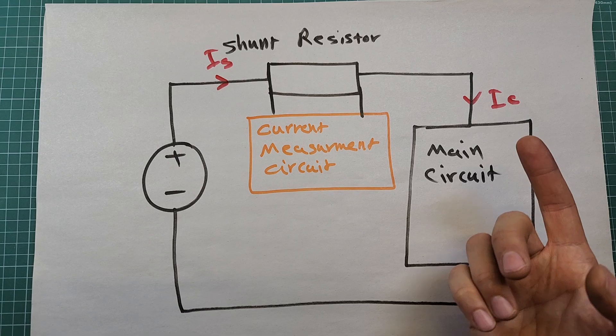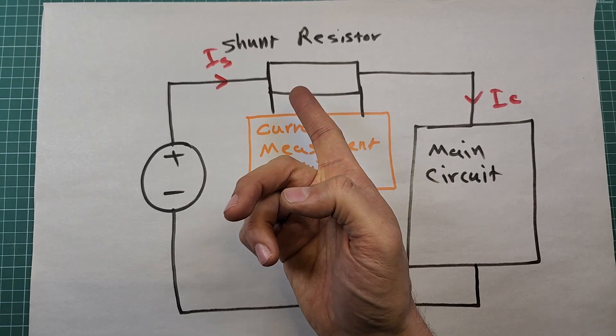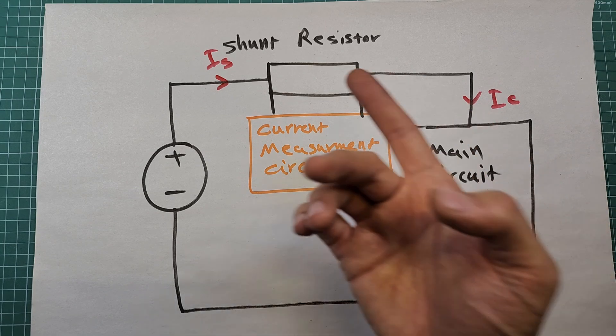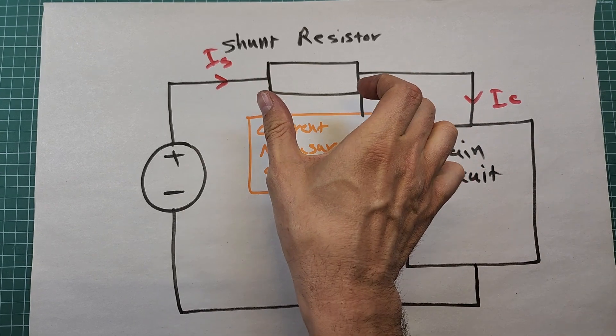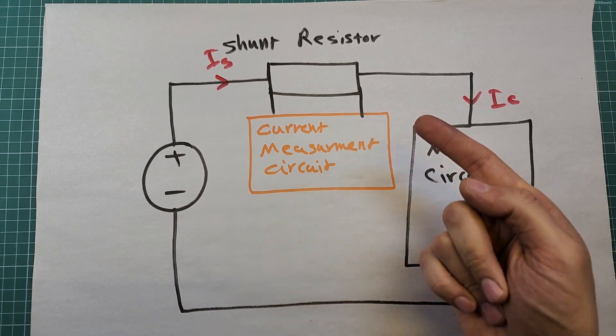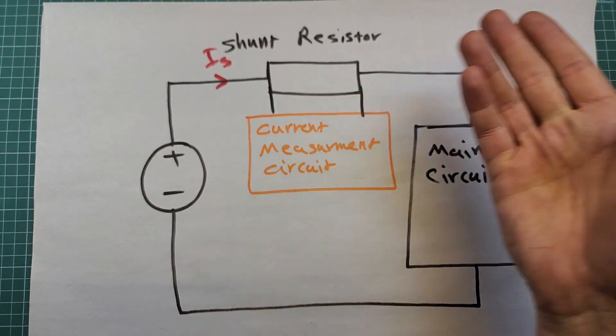In many cases using a shunt resistor is the best method, but it also has disadvantages that make us not want to use it in some cases. One main disadvantage is that a resistor is added to the path — no matter how small it is, it may negatively affect the performance of the main circuit. For example, if a large current passes through the shunt resistor, it causes the voltage across it to increase, and this voltage drop is subtracted from the voltage of the main circuit.